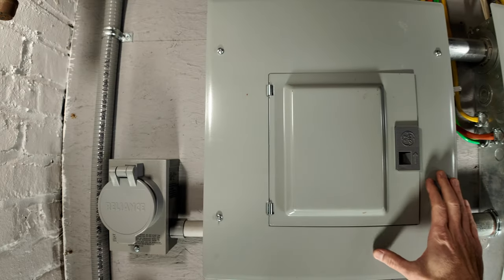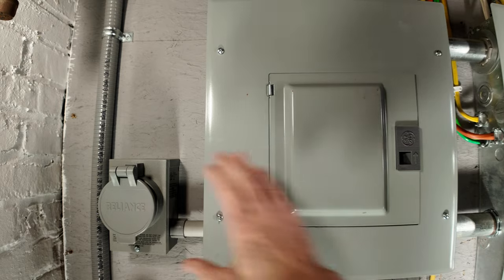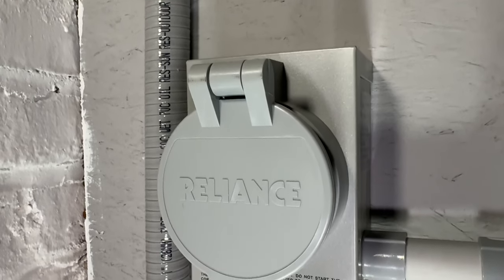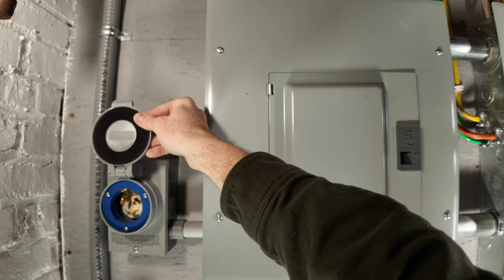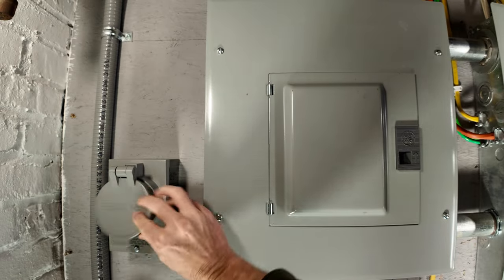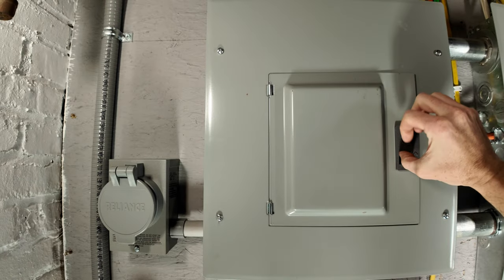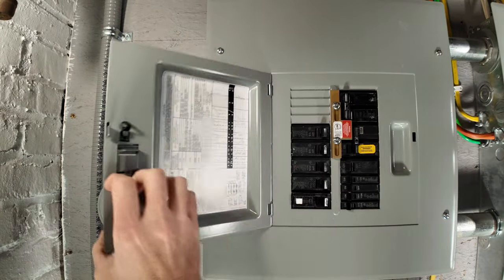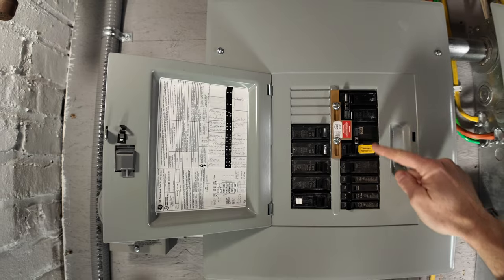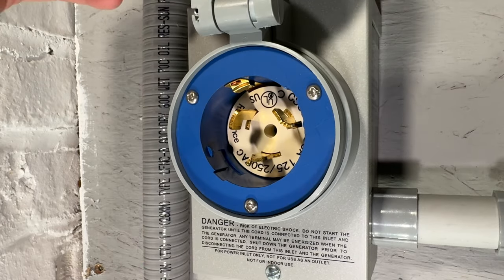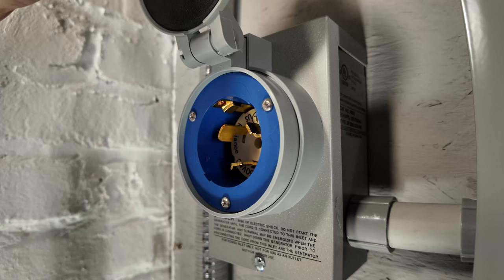The way we get power into this panel is through a power inlet port. This allows me to plug my power station into this port here, and the wires connect through here into the panel and connect to these breakers. I installed a 50 amp power inlet to be future-proof, but since the EcoFlow Delta Ultra only puts out 30 amps with a single unit, you could do a 30 amp input.